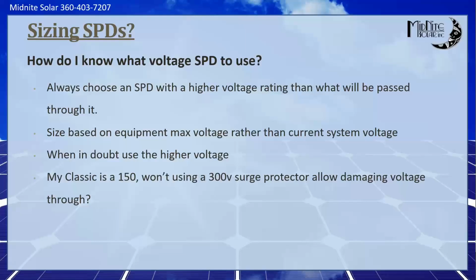But keep in mind that every piece of gear that's UL listed has been run through a test we call high pot testing. And that high pot testing basically runs several thousands of volts through the device to make sure that it doesn't bleed to the chassis anywhere. It's a test we all have to do on every piece of equipment. A Classic 150, for example, is high potted to about 2,500 volts, and that is not allowed to bleed through to the chassis anywhere. And if it does, then it fails.